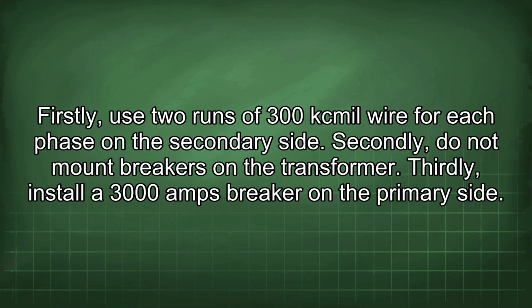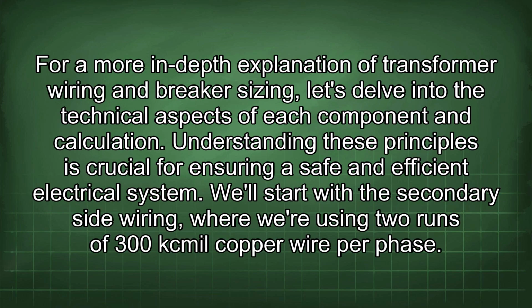Firstly, use 2 runs of 300 kcmil wire for each phase on the secondary side. Secondly, do not mount breakers on the transformer. Thirdly, install a 3000 amp breaker on the primary side. For a more in-depth explanation of transformer wiring and breaker sizing, let's delve into the technical aspects of each component and calculation. Understanding these principles is crucial for ensuring a safe and efficient electrical system.